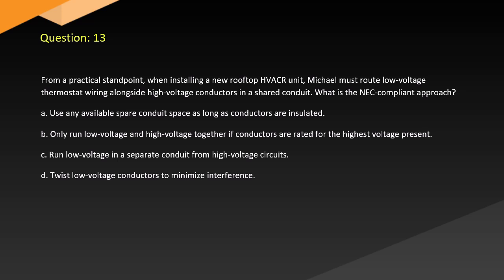Question 13. From a practical standpoint, when installing a new rooftop HVACR unit, Michael must route low-voltage thermostat wiring alongside high-voltage conductors in a shared conduit. What is the NEC-compliant approach? A. Use any available spare conduit space as long as conductors are insulated. B. Only run low voltage and high voltage together if conductors are rated for the highest voltage present. C. Run low voltage in a separate conduit from high voltage circuits. D. Twist low voltage conductors to minimize interference.